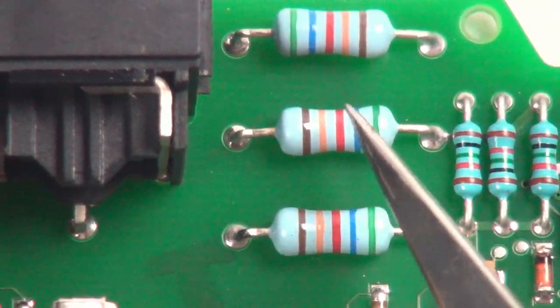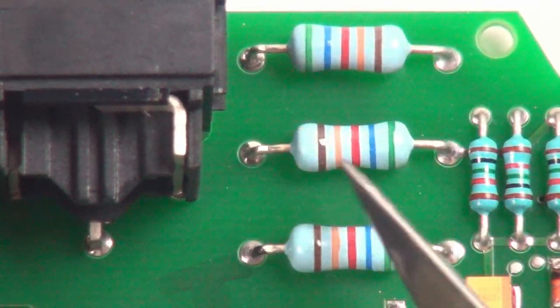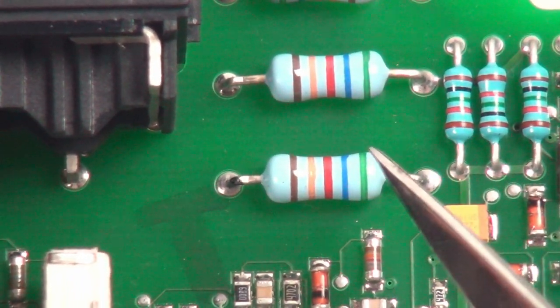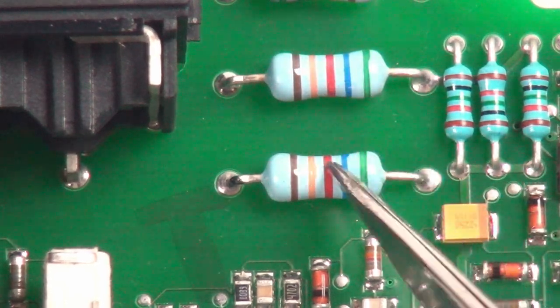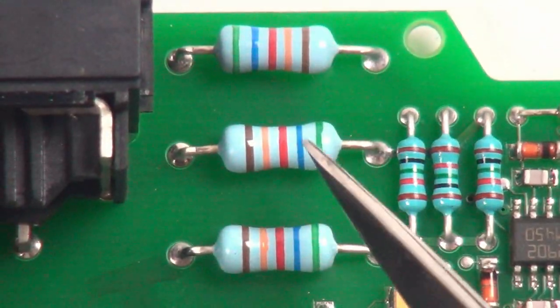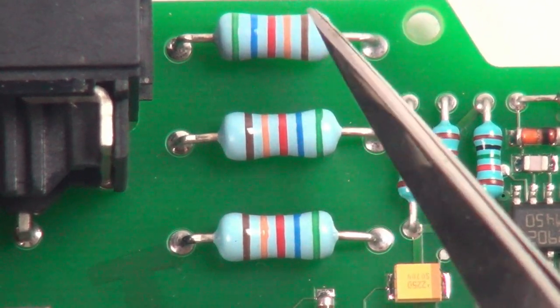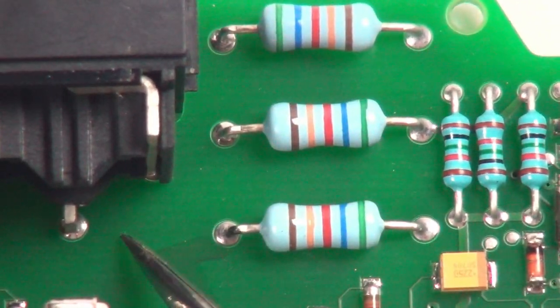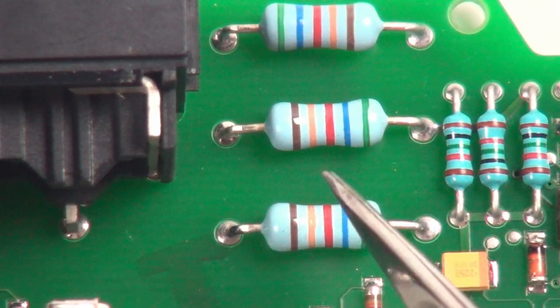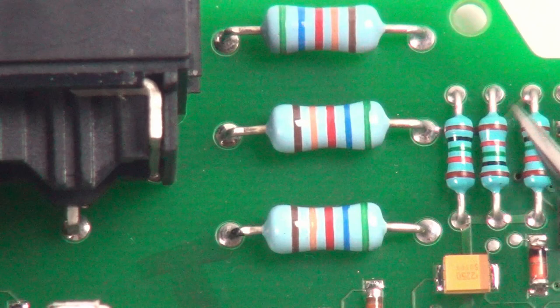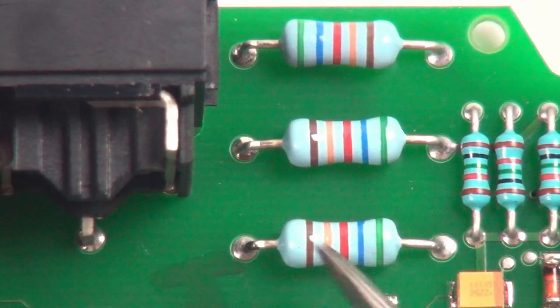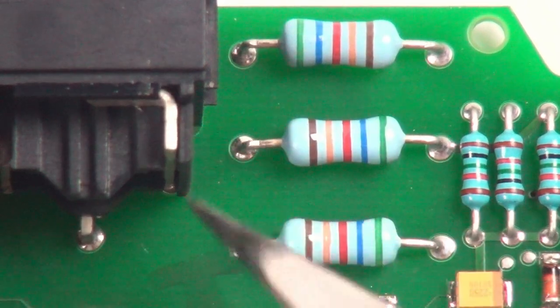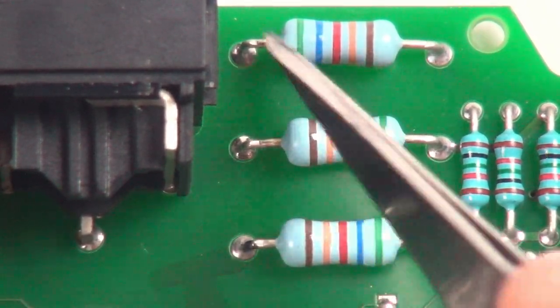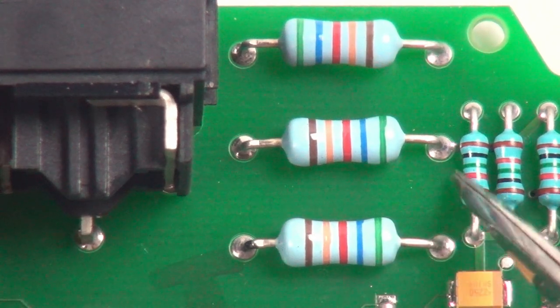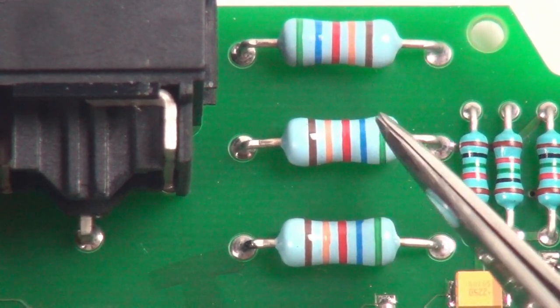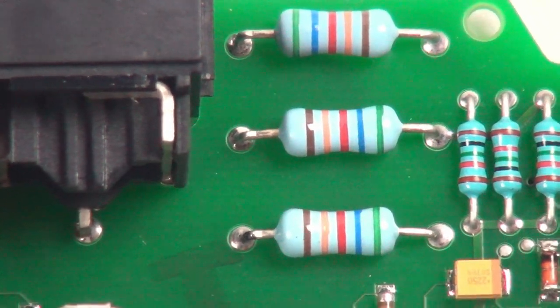I don't have the band colors memorized, but these are most likely a fairly high value resistor because these resistors are protecting the front end from damage, basically from high currents. Because if you're missing a phase, you can get an imbalance in here, and these resistors will protect the front end over here from high current flows. Because if one phase is, let's say, 50% of the other two, you can get a high current flow that goes from the two phases down to the middle one, and these resistors will prevent that from happening.